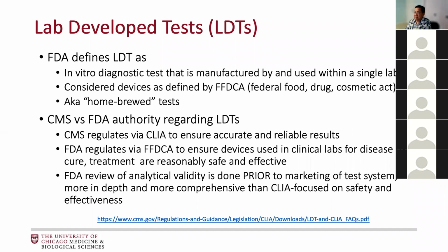So the CMS regulate and FDA do what I call a sort of dance around the LDT. By definition, FDA has authority on all in vitro devices. So LDT is an in vitro device. So by definition, FDA has regulatory oversight over LDTs. But because no university hospital has the resource to get an LDT approved, the FDA, even though it does have the authority, sort of exercises discretion, meaning that it turned a blind eye on it right now. Okay, exercise discretion means exercise not to regulate it at this point.